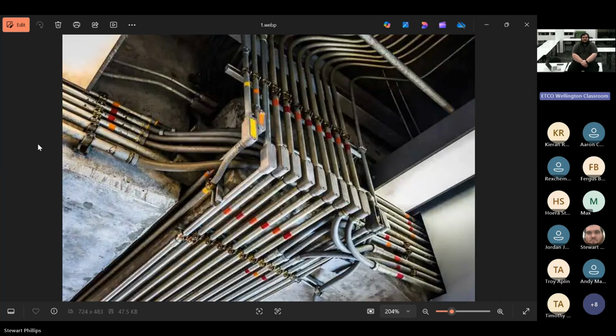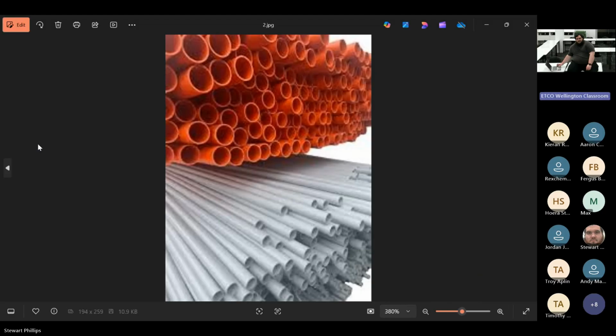So yeah, one thing you have to remember though with steel conduit, if you run a live cable inside of it, you need to bond it just like any other exposed metal wiring container. Enough about steel conduit. If you guys do industrial or go over to the mines, you will come across it. But if you're just doing general commercial and residential, it's less likely that you're going to come across it. But it is still possible.